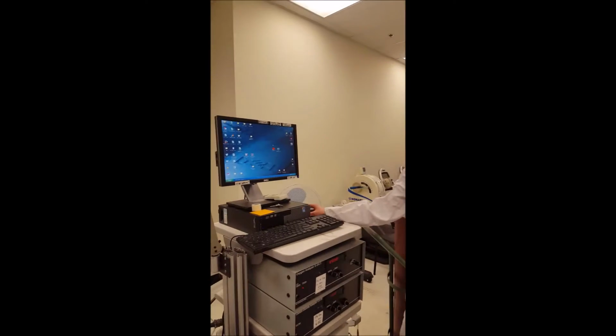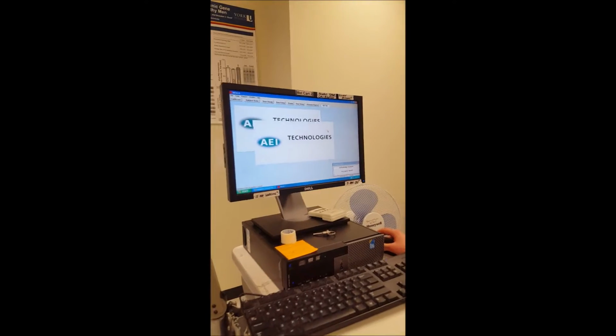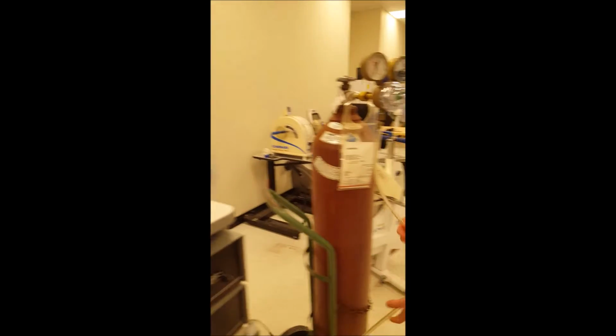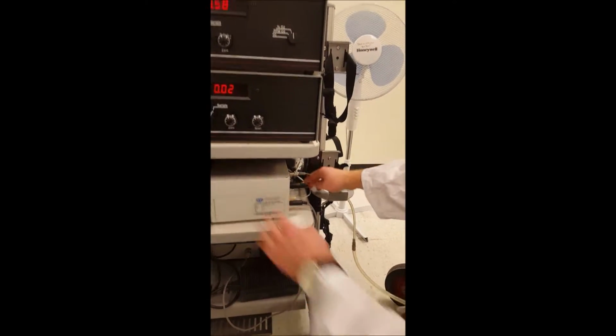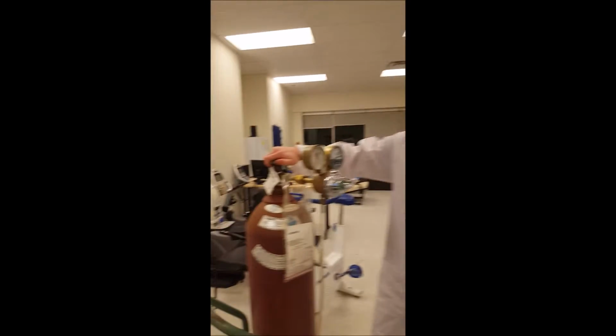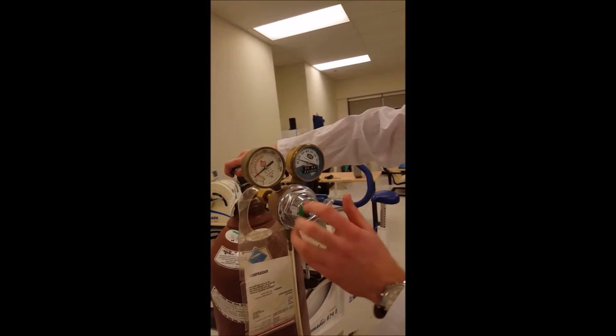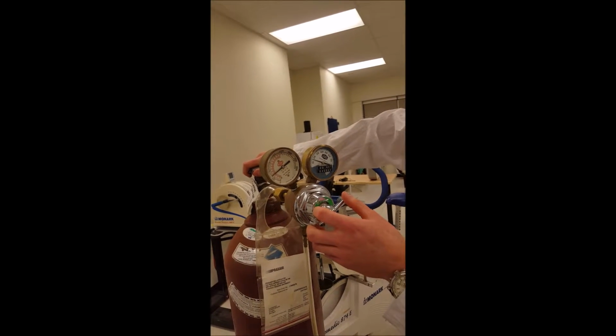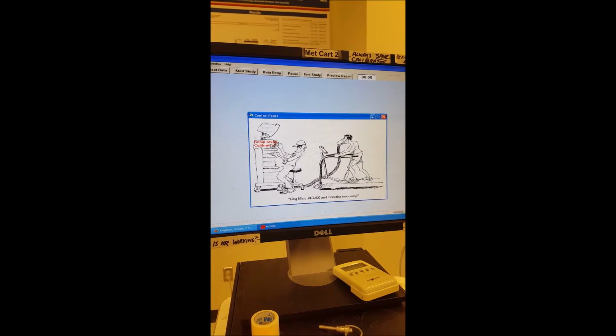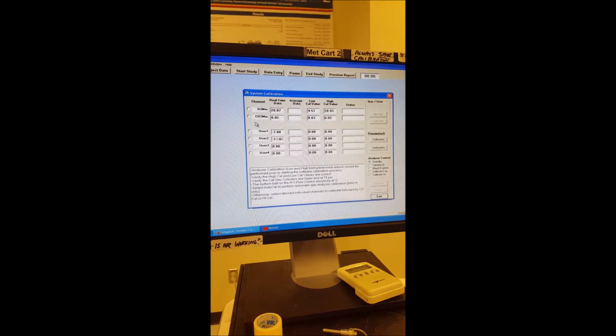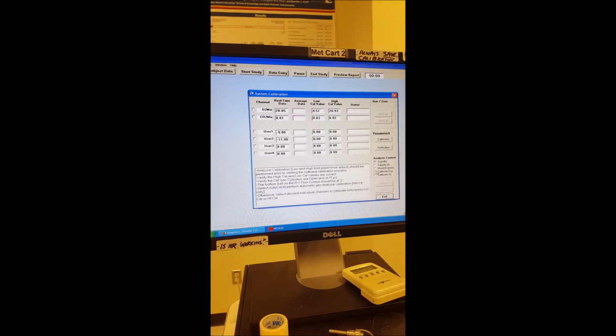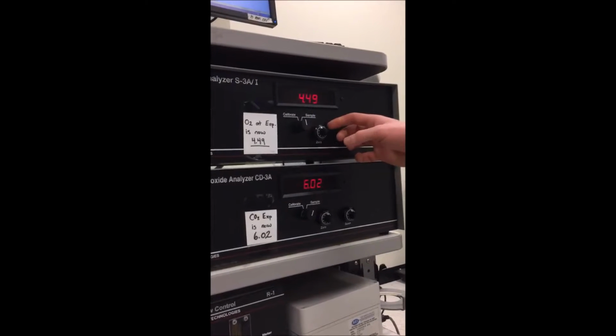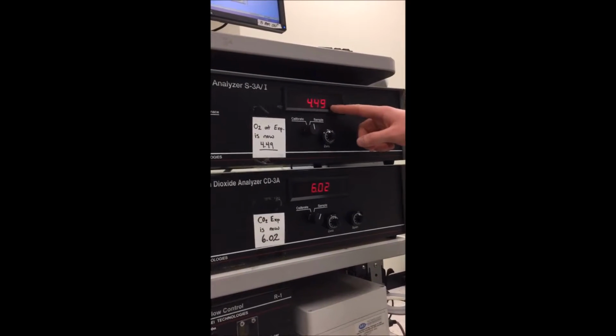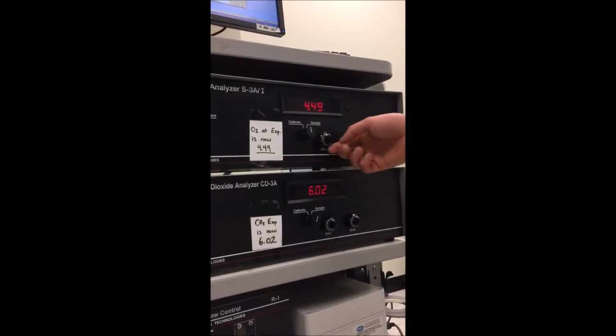Alright, so the first thing we do here is open up the Moxus system on the computer. While it's loading, you can follow this tube down to the back and plug it in nice and tight to the computer. Once it's plugged in tight, open up the valve slowly and ensure that the valve's at 15 psi. Now we select Setup Study Calibration and click Calibrate Expired. So the next thing we do is switch these dials to calibrate and ensure that the numbers, as you can see here, are the same listed on the machine.